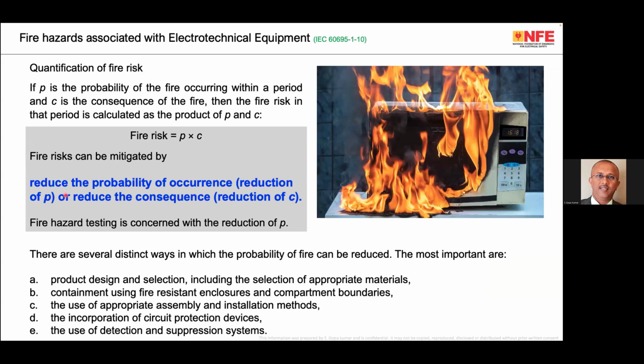The quantification of fire. Fire risk is the probability of occurrence of fire multiplied by the consequence, the number of fire accidents into the consequence. Fire risk can be mitigated by a reduction of the probability of occurrence or a reduction of the consequence. Reduction of consequence is not in the hands of the electrical designer or engineer, whereas reducing the probability of occurrence is very much in the hands of the designer. If the designer of an equipment or installation, or an engineer who installs, maintains or verifies the installation, can very much reduce the probability of occurrence, thereby reducing the chance of fire.